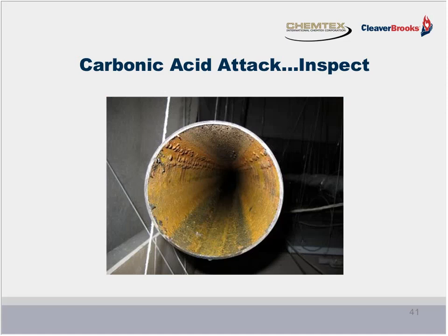The other thing is that I think it's always worth mentioning, you've inspected the boiler, why not inspect the condensate line? Look to see if there's a groove starting to show in the bottom of your condensate pipe, and look in different parts of the plant. Oftentimes there's a flat run of pipe right near a condensate receiver, which would allow you to inspect the condensate line, because there's a union right there and a horizontal run of pipe that would allow you to inspect that piece of pipe. Be proactive.